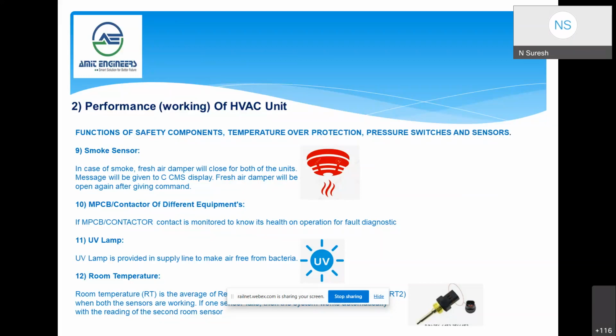This system has MPCB contactors, and the interesting point here is that this unit has a UV lamp in the return air path, through which the return air and fresh air pass. Over a period of time, the return air will be purified to avoid any bacteria. The UV lamp is also placed in front of the filter, so that if any bacteria is forming in the filter, it will help reduce the bacteria.